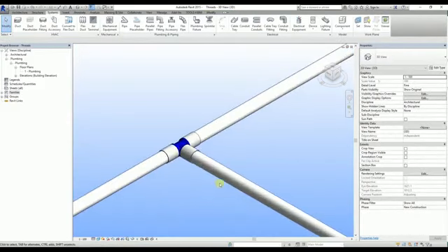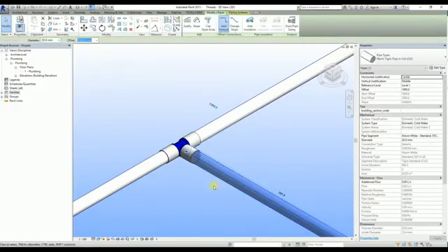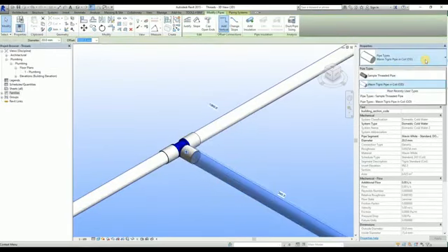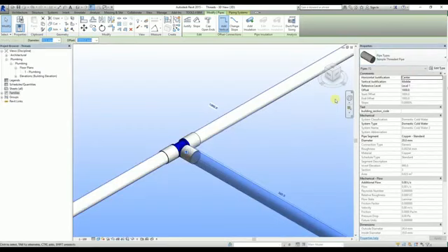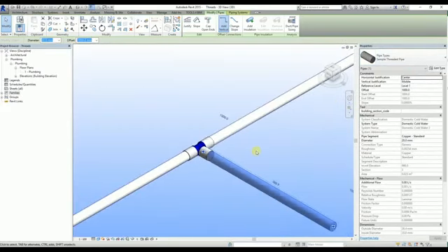Now let's say that I want this pipe to be ended with a thread. I select it and change its type into a sample threaded pipe. In this case, the nominal diameter is the same as the outside diameter of the Tigris range. Let's change its diameter into an inch value. In this particular project, the inch value is shown as 19.1 millimeters, which equals 3/4 of an inch. Let's use it.